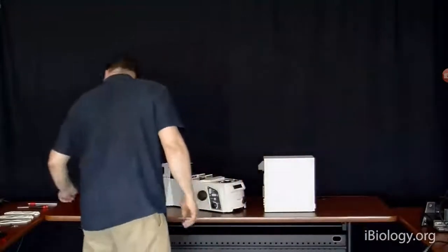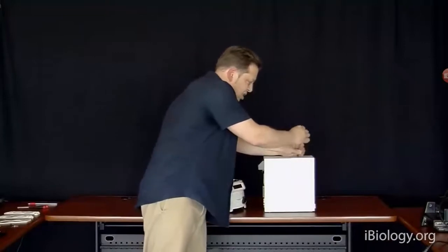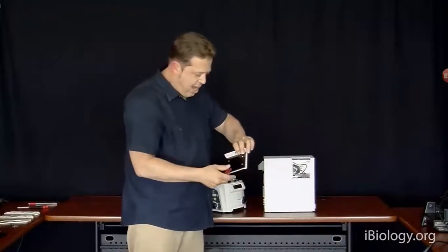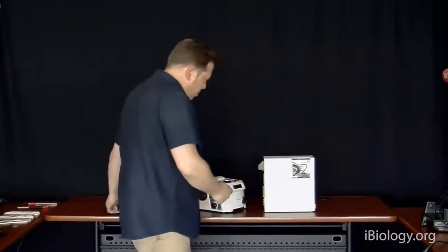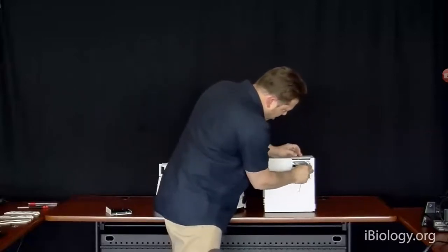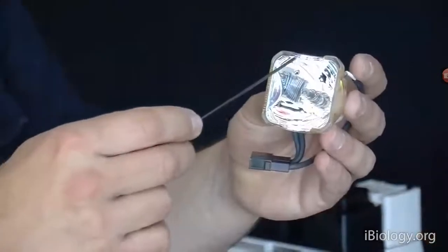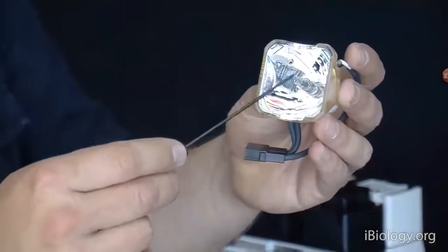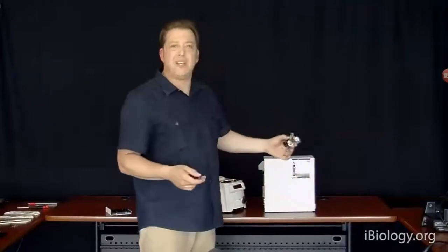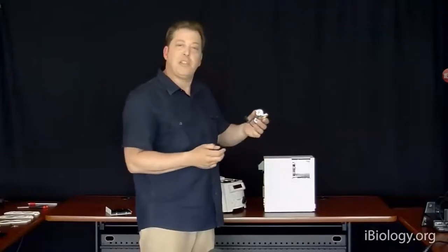And inside here, we actually have the bulb, just like with the halogen lamp house, very heavily insulated. And beyond that, we have bulbs that you can pull out. Again, you never want to touch any of these bulbs with your fingers, but you can see this bulb actually has a parabolic reflector around it, and it's a metal halide bulb in this case. We can use LED sources, metal halide, xenon, mercury, and so on. This one, again, happens to be metal halide.